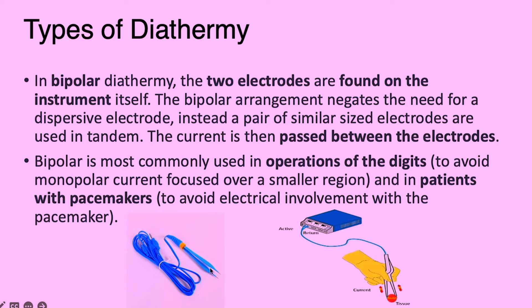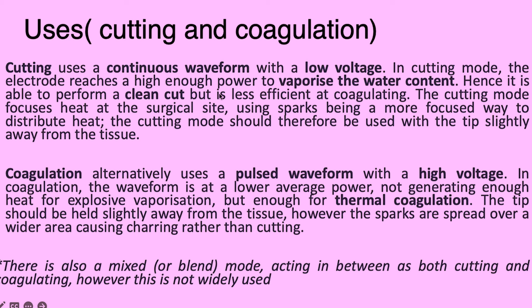The bipolar arrangement negates the need for a dispersive electrode. Instead, a pair of similar-sized electrodes are used in tandem and the current is passed between them. Bipolar is mostly used in operations of the digits to avoid monopolar current focused in a smaller region, and is used in patients with pacemakers to avoid electrical involvement of the pacemaker.